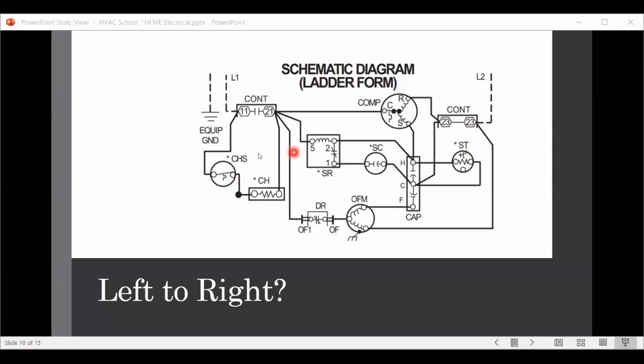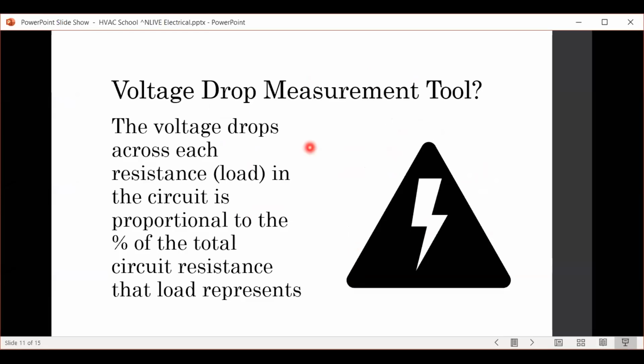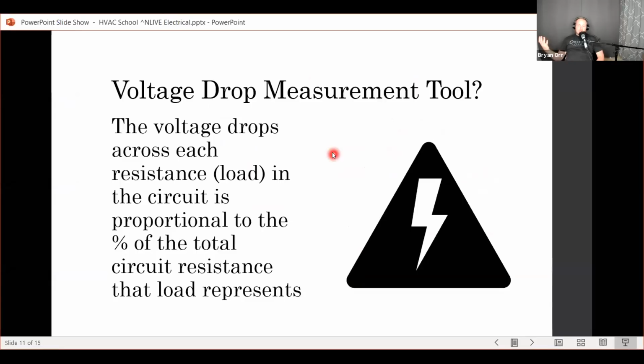Yeah, that's a lesson to test that you may be going back behind another technician. You may be putting on the fourth contactor in the lifespan of that unit. It might be a good idea just to check the wiring diagram and make sure that you're putting on the right style of contactor before you just put on what was already there. Yep, absolutely. And this is actually something we've talked about a lot in the past when those were more common, because that's not actually stock on most units even that come with that wiring diagram. That's sort of a generic wiring diagram, and they have a little star that this may exist. You don't see that in the field as often as you once did, and so it's not as big of a deal, but there was a time when that was actually quite common. That is an issue, and you have to pay attention to those details.